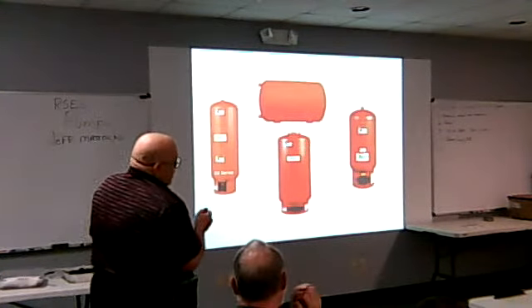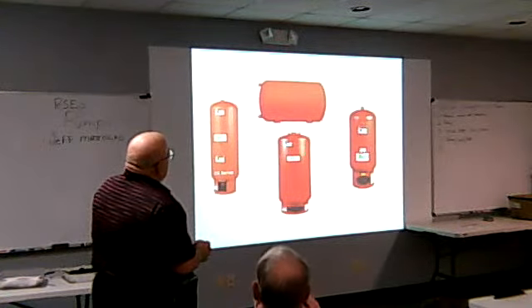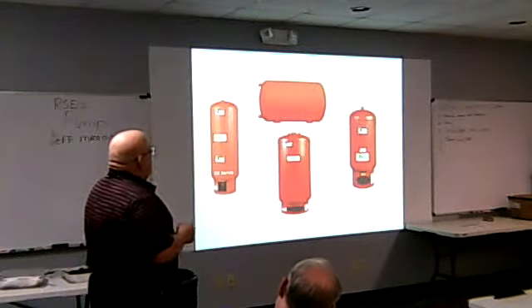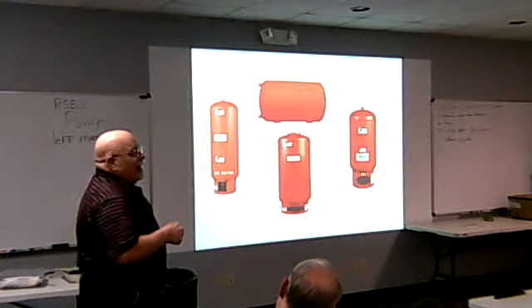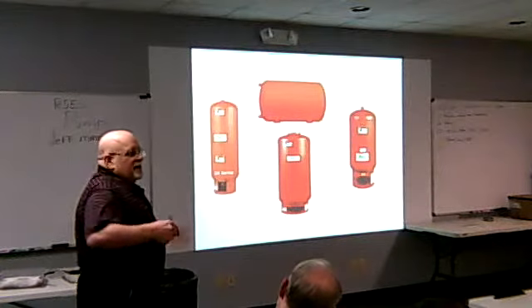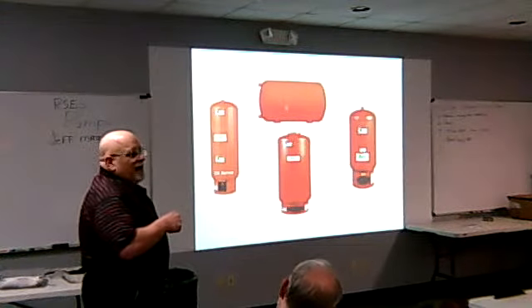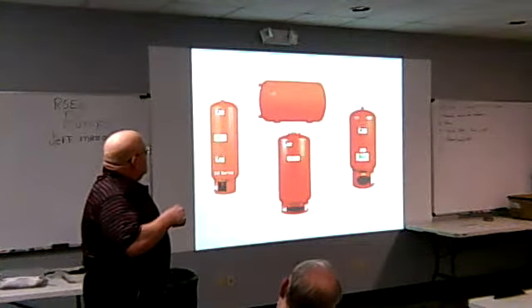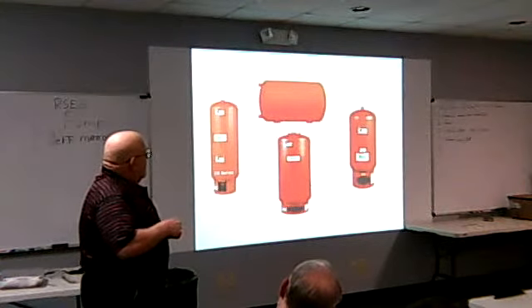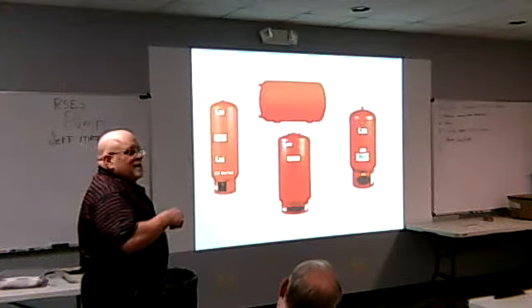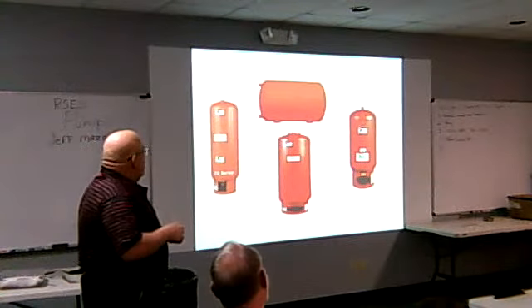Okay, these are examples. This is your plain steel tank with a gauge glass. Like I said, atmosphere. So when you first put pressure on this, it's going to fill halfway up. Your gauge glass is going to compress that 14 to 20 psi and stop. And eventually it's going to waterlog. You open the drain, let the air back in, realign it.